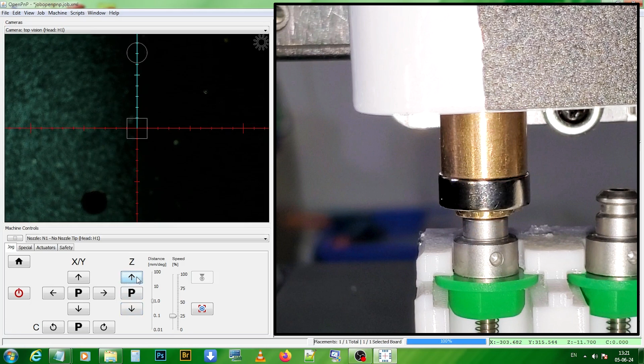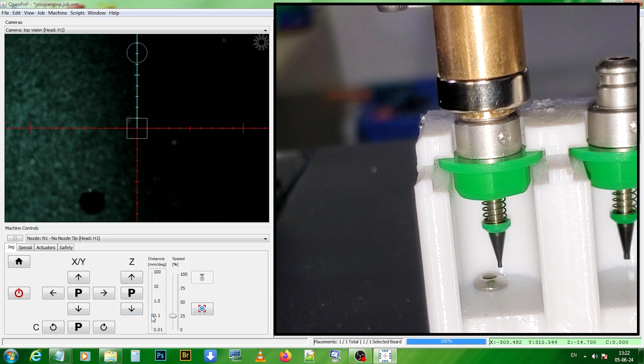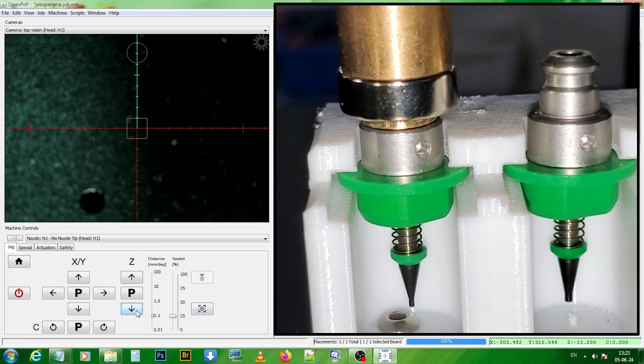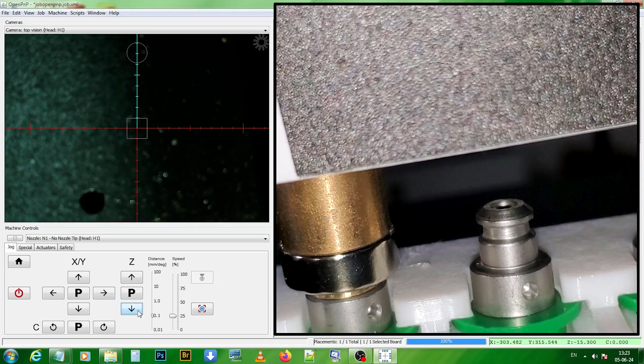Then I change the steps to 1 millimeter and I start to go down. I check if the tip is free to move. If it is not, it means it is forced against the holder because the alignment is not good. Then I change again to 0.1 steps and I go down checking if the tip is free to move. It doesn't have to go all the way down. Minus 15.4 millimeters is okay for this tip.